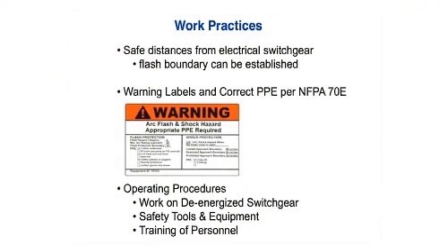All right, we were asked many times, why can't a manufacturer put a warning label on switchgear? And the obvious answer is, we don't know the application. If we knew all the parameters of the application, hell, we can do the 1584 calculations as well as y'all can. But we can't because we don't know the application. That's why we can't put the labels on the switchgear. Okay?